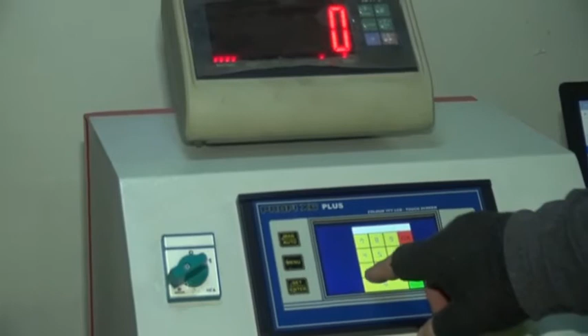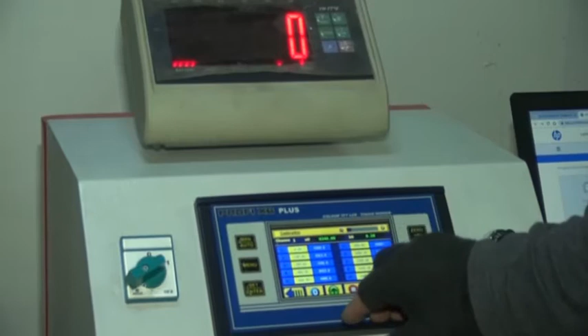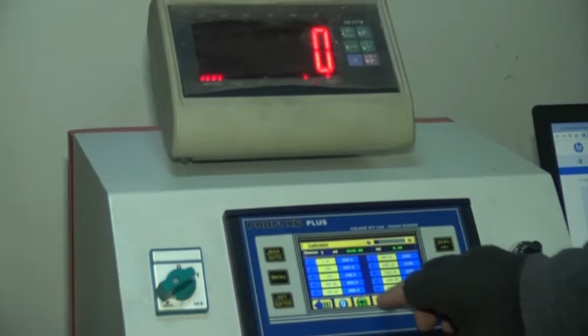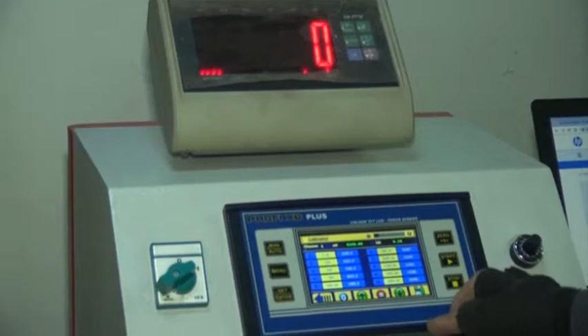Now we have a table here. The yellow boxes on the left side show the reference values in kilonewton. On the right side, the blue boxes show the millivolts, the raw measurement data. For that reason, I'm going to prepare the reference values first. For example, if I start with 100 kilonewton, I press the yellow box and enter 100. And for the second step, 200. And the other step, 400.